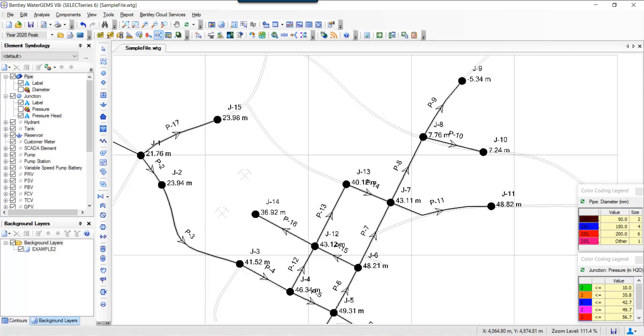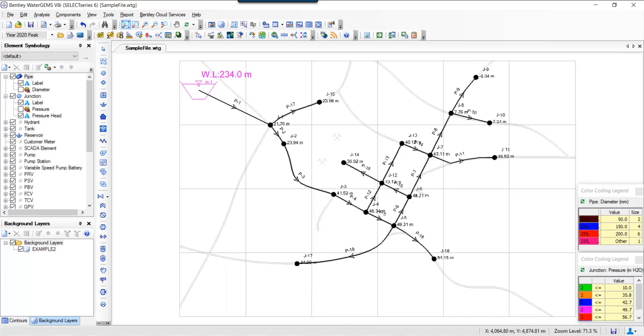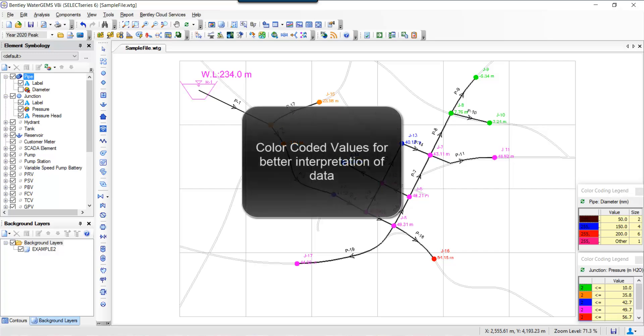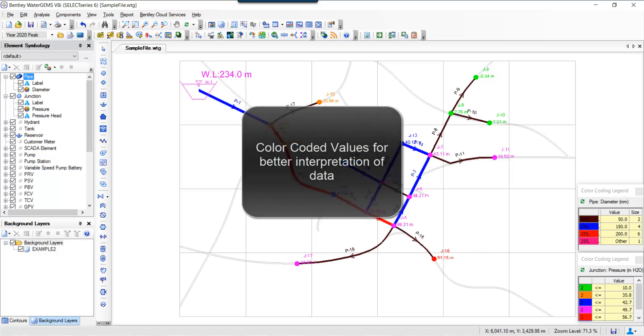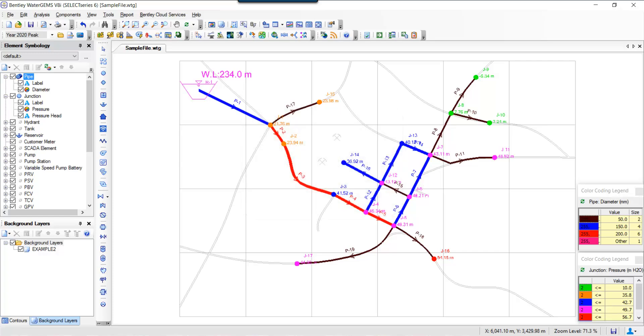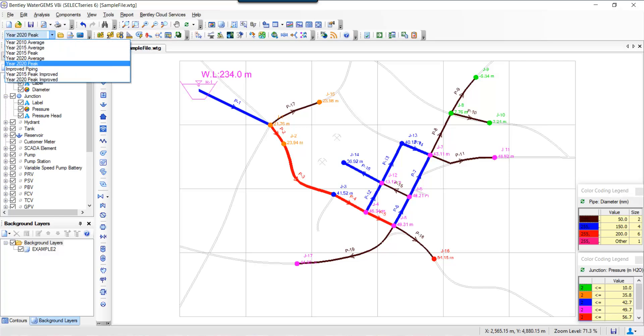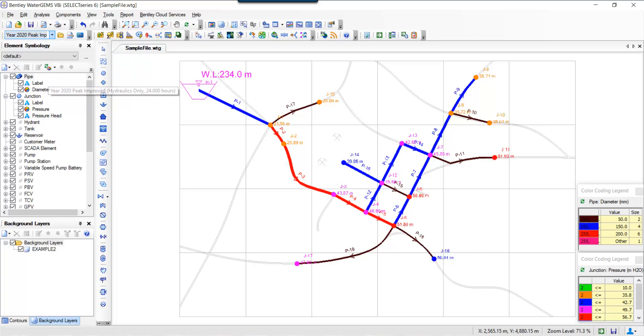And you can also set up your color coding for better interpretation of the data. So right now I'm going to change my scenario to basically change diameters and reflect the improved system. So I'm going to change it to 2020 peak improved. The diameters are now 150 mm at the ends. So now let's recompute the data and see how it looks.